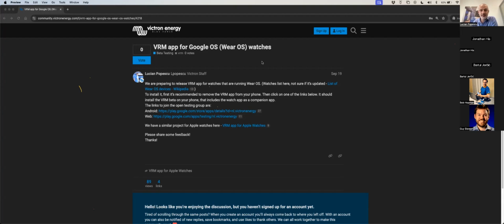Anything for the US market, 220 volt, 60 hertz? I have no idea, but even the current version can work, and I think there have already been some experiments for the US. I know from my US colleagues it was tested and it's working. The only issue is powering the contactor from 2 phases instead of phase-neutral, because the coil of the contactor is designed for 230 volts. So you either change that contactor inside and power it between neutral and one phase, or power it from both phases, and it should work. But again, it's a DIY thing - they can do it but with no support from our side, or they can wait for the new version.